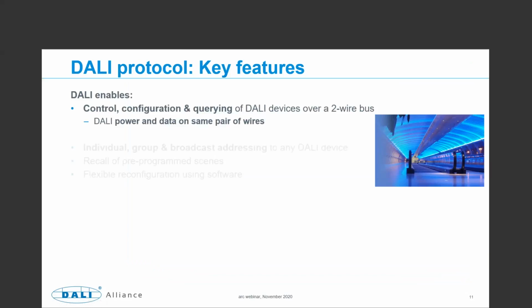Now, DALI provides individual, group, and broadcast addressing to any DALI device. And you can recall pre-programmed scenes. So very efficiently, you can send one command, a scene recall command, that affects some or all of the control gear, all of the luminaires in the system. And this is flexible, so you can reconfigure using software. You don't need to change the wiring.